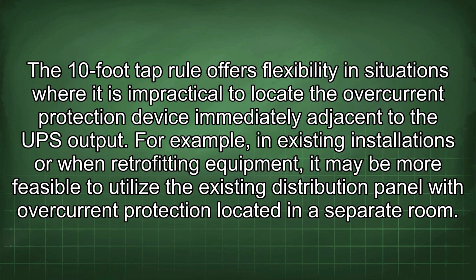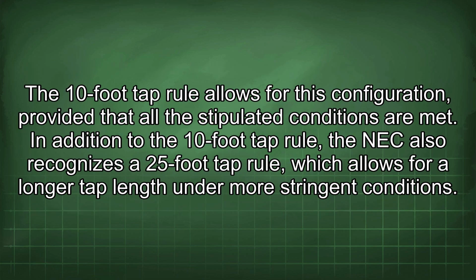For example, in existing installations or when retrofitting equipment, it may be more feasible to utilize the existing distribution panel with overcurrent protection located in a separate room. The 10-foot tap rule allows for this configuration, provided that all the stipulated conditions are met. In addition to the 10-foot tap rule, the NEC also recognizes a 25-foot tap rule, which allows for a longer tap length under more stringent conditions.